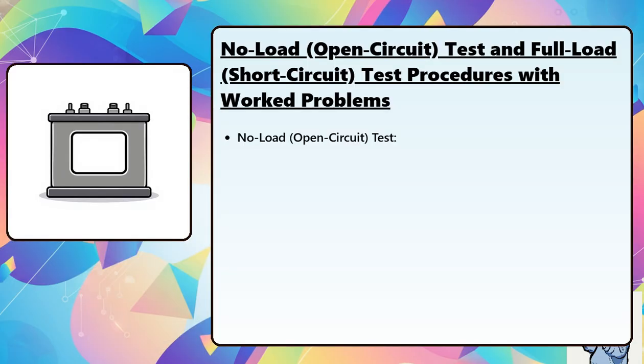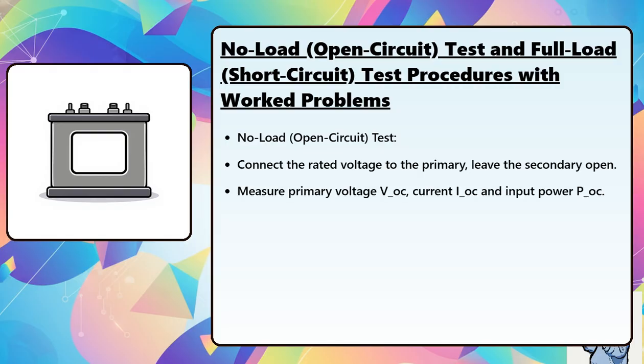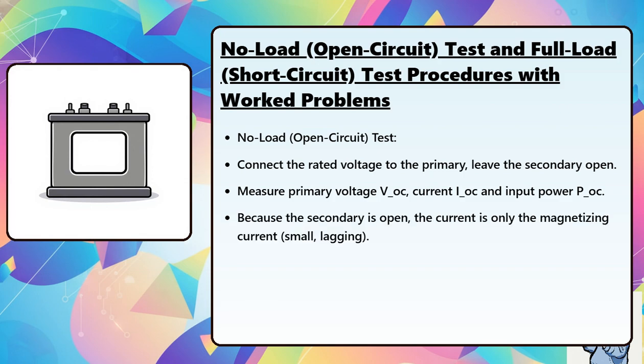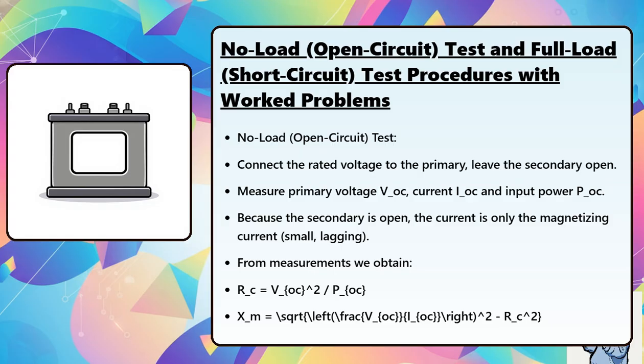No load open circuit test. Connect the rated voltage to the primary and leave the secondary open. Measure primary voltage V sub OC, current I sub OC, and input power P sub OC. Because the secondary is open, the current is only the magnetizing current, small and lagging. From measurements we obtain R sub C equals V sub OC squared divided by P sub OC. X sub M equals the square root of the quantity V sub OC divided by I sub OC, squared, minus R sub C squared.